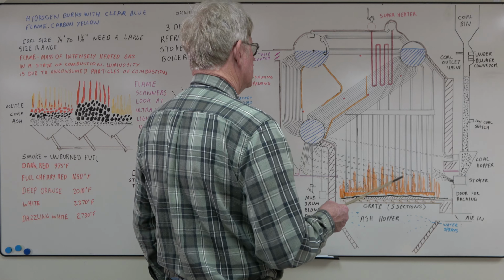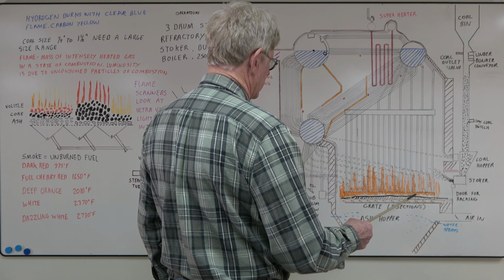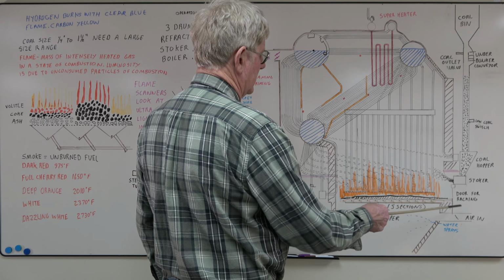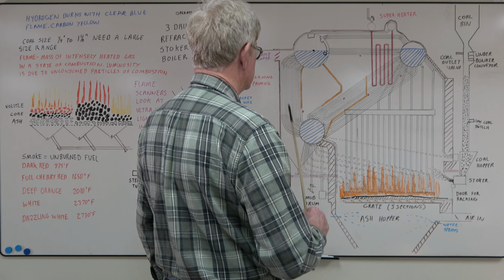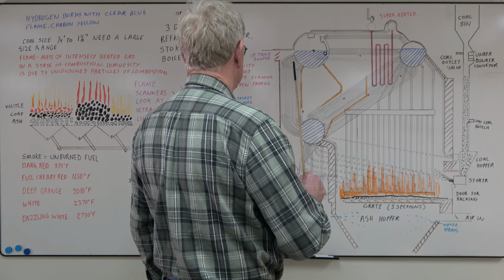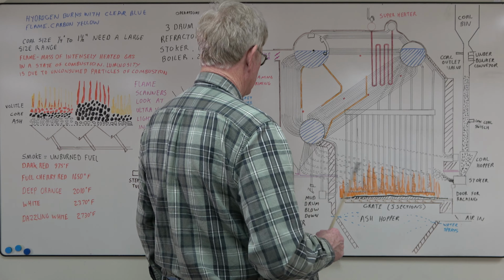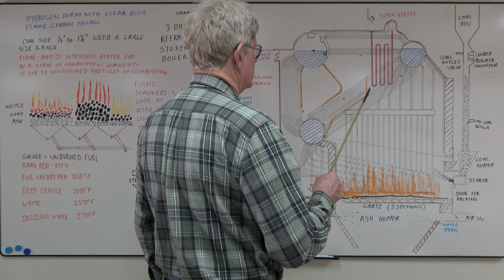To blow soot, you wouldn't blow soot on a banked boiler if it wasn't running at pretty good load. You open your uptake dampers all the way, crank your air up. You have to have good airflow to get rid of any unburned gases out of here. And then you just start blowing it back across the boiler, keeping the soot and ash moving back. Bigger stuff would drop out in your hopper, then return to the boiler. Now you'd blow soot probably once a shift.